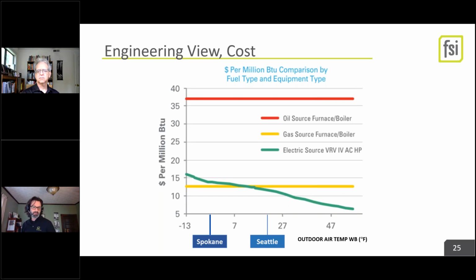Also a note on the cost, because one of the things we hear a lot is, you took away my cheap heating with gas, and it's a yes and. Because the heat pump is 3.5 or 4 times as efficient as regular gas heating because of its COP, even at its design temperature, which we don't run every day at design temp, it's about at parity with gas furnaces. And it's certainly 2.5 or 3 times better depending on the equipment for electric resistance. And oil costs more. We don't see a lot of oil nowadays anyways, fuel oil systems. But on a cost basis, we're kind of at parity. That argument doesn't much hold water either.